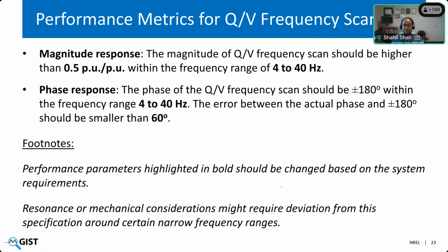So what are the performance metrics for Q by V frequency scan? So first is the magnitude of Q by V frequency scan should be higher than 0.5 per unit by per unit. Again, this is an example number. What it really shows is that the dynamic short circuit ratio that I talked about is 0.5. Basically, 100 megawatt grid forming BESS would contribute grid strength of around 50 megawatt. In reality, as I showed in the previous example, the grid forming BESS provide this gain of around 2.5 to 4.5. So you can demand this gain to be higher.